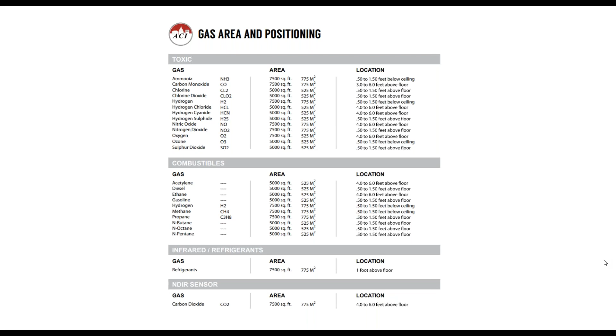Just the gas positioning thing again, low, medium, and high. Low is usually 12 to 18 inches off the floor. Medium is 4 to 6 feet, and high, below the ceiling, is anywhere from half a foot to 2 feet, somewhere in that range too. It gives you square footage of coverage, same with the radius and stuff like that. Every gas is a little bit different depending on its weight. So for some of the applications here, we'll talk about parking garage. Of course, you mount your NO2 down low, and you mount your CO at 4 to 6 feet.